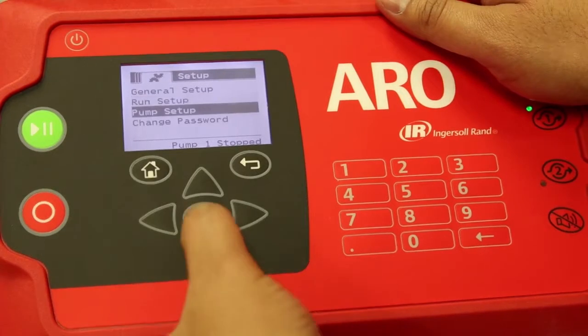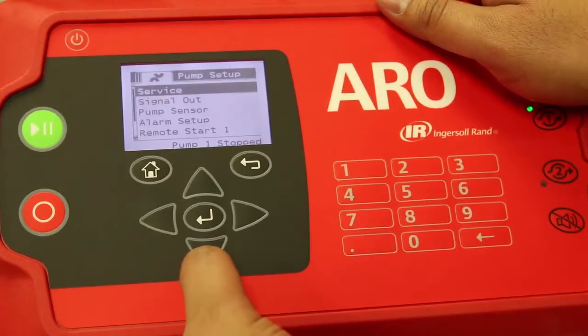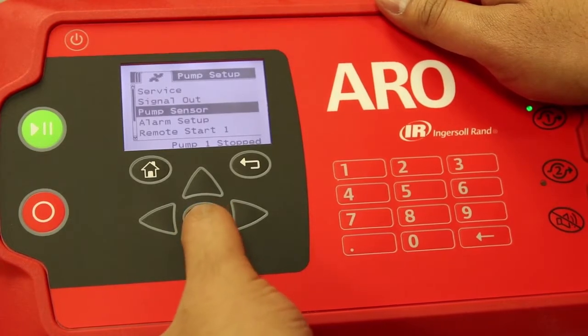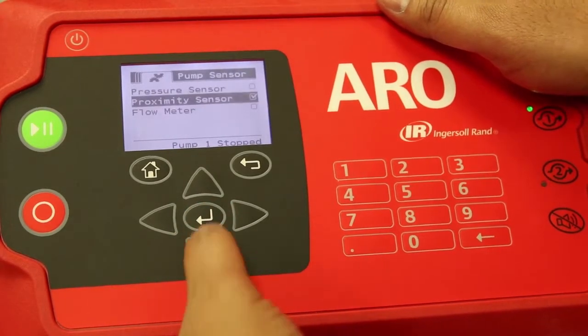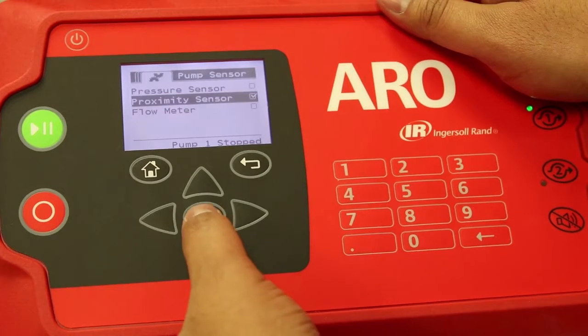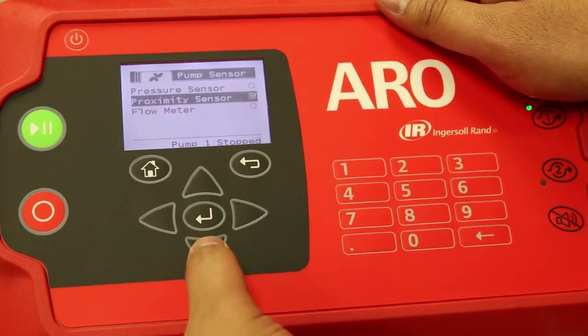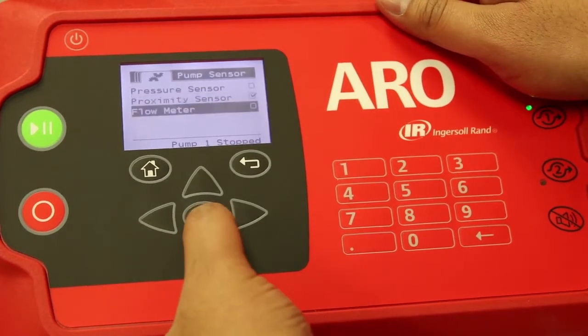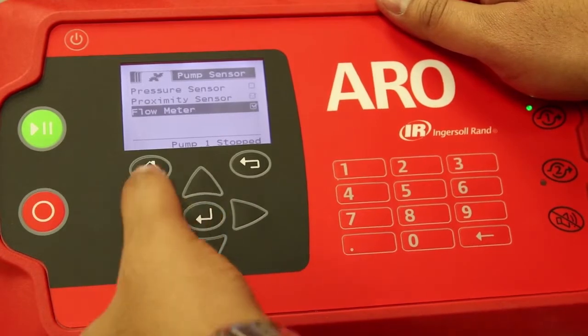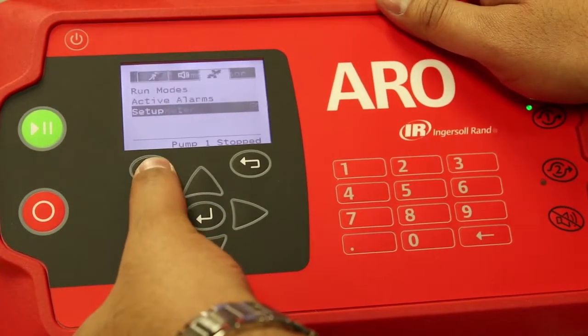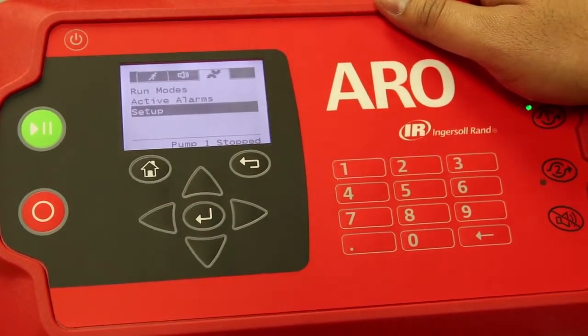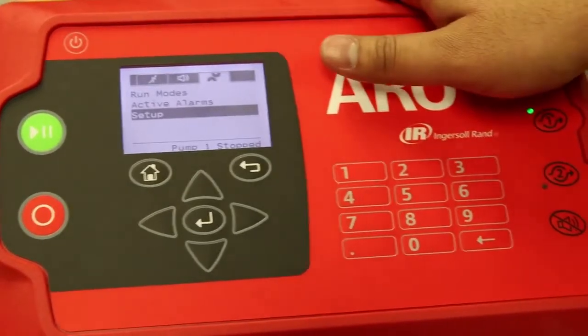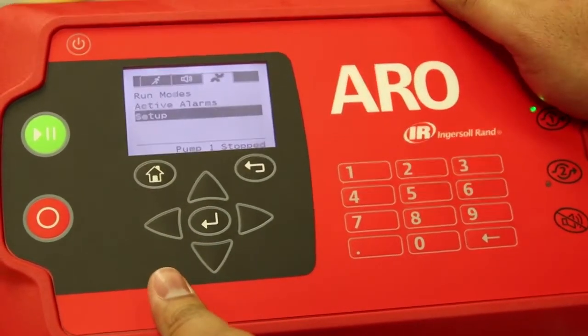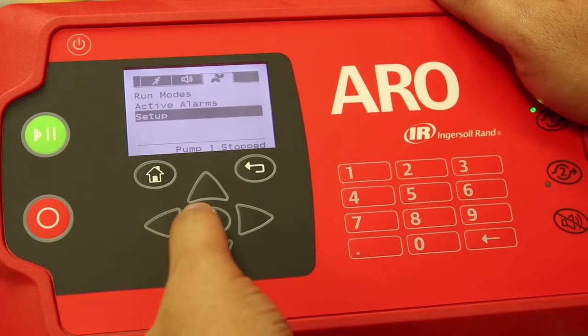Next step would be to select a pump sensor, and to do that, we go into pump setup and go into the pump sensor menu. You have three options: a pressure sensor, a proximity sensor, and a flow meter. Select flow meter, and that lets the controller know that we are interfacing the flow meter with the controller.